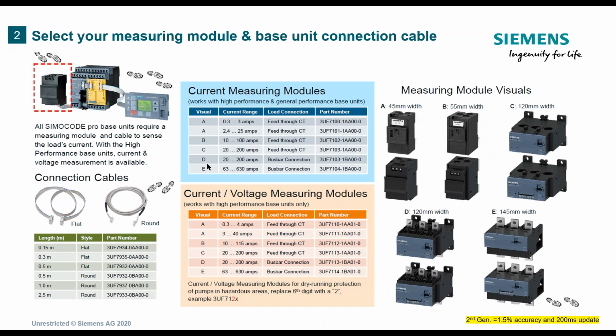Now, I have an application in California that does 800 amps with the SIMOCODE. We have the ability to stage or put a standard CT and make that a primary CT. And then in the SIMOCODE, you check a box to look for the secondary CT, and then you put in the ratio, and I can go up to 800 amp measurement. And what I did with that one is I did an 800 amp measurement with the primary CT, just an off-the-shelf split core CT, and then I put in a 2.4 to 25 amp PTC or PT or CT for that application here of the SIMOCODE. And then the cables that connect them.